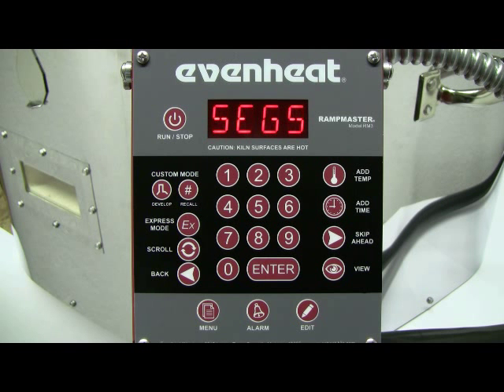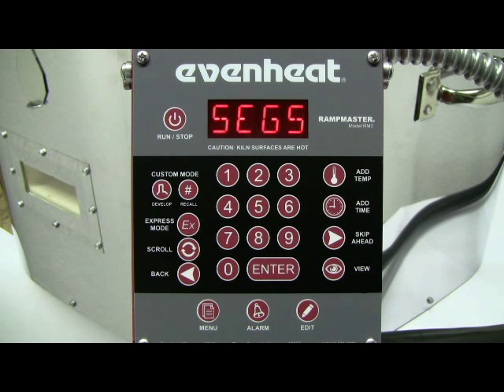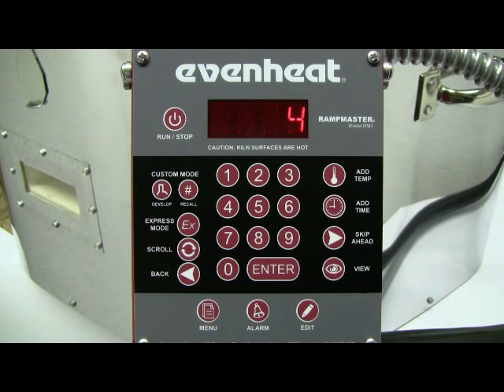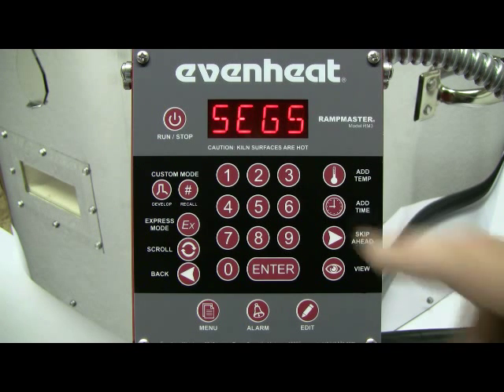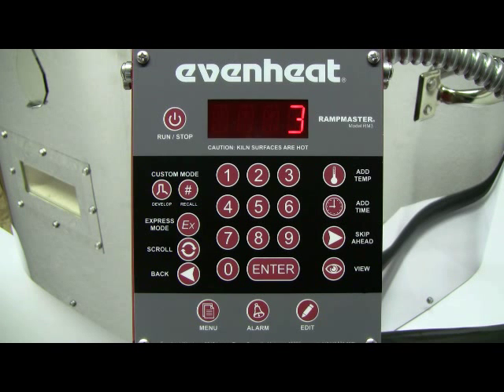The RampMaster is now asking for the number of segments you would like to use for this program. A segment is a combination of rate of temperature change, the desired temperature, and any hold or soak at the desired temperature. For our example, we want to use 3. Type in 3, then press the ENTER key to store your choice.